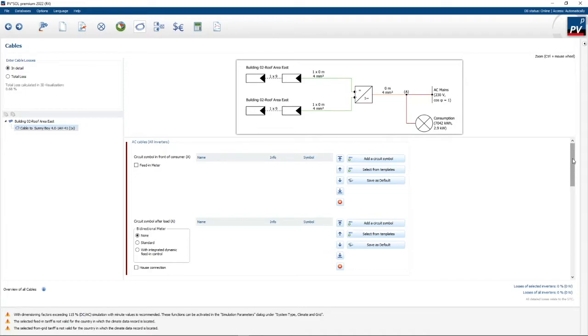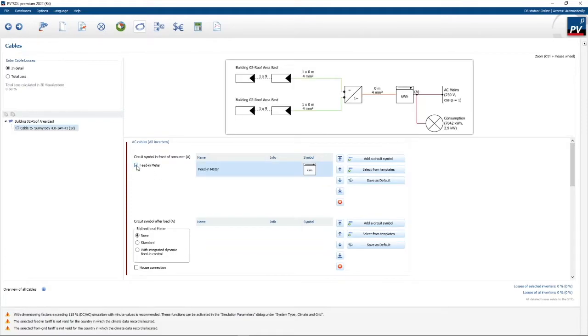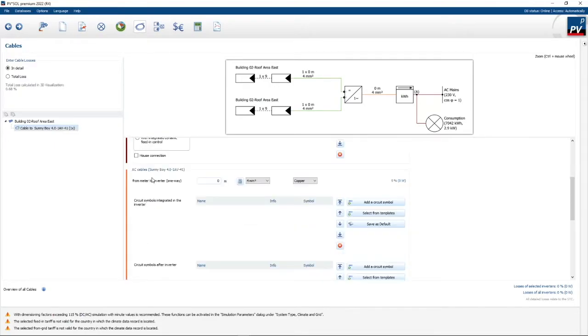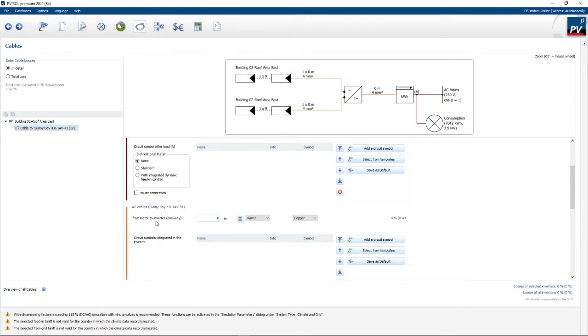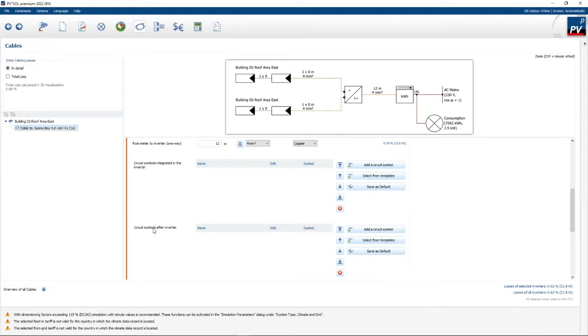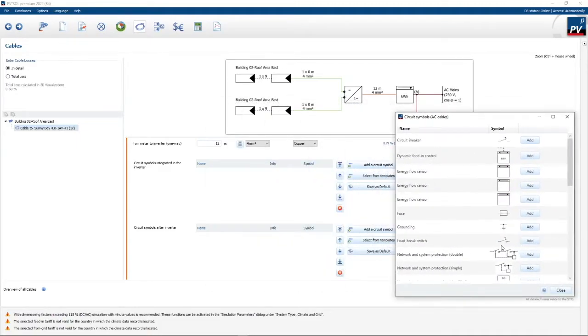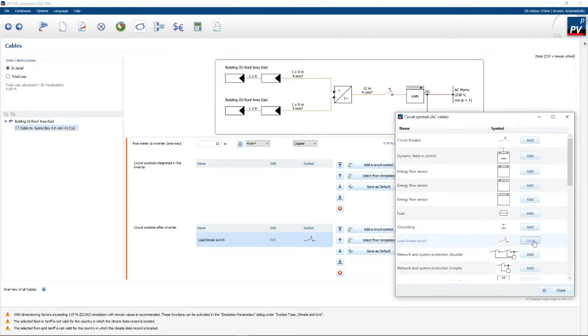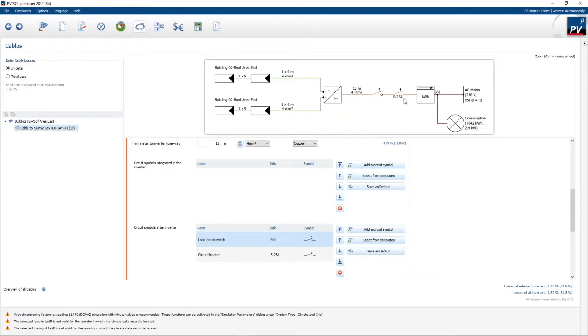Normally what we want to do is add a few things. We want to feed into the grid, so I'm going to add a feed-in meter. I also want to specify my cable length from the meter to the inverter — let's say 12 meters. If I click the little calculator, it tells me I need a 4mm² cable. Then I want to add some symbols after the inverter: an isolator (load break switch) and a circuit breaker. PV Sol will size the circuit breaker according to the cable thickness and distance.